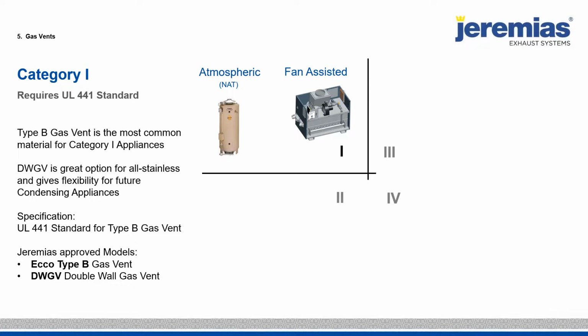So really what these categories tell us is what type of material to use on the venting side. So category 1 requires UL 441 standard. So that's type B gas vent. So UL 441 is a type B gas vent that can only be used on category 1 appliances. So we have a type B gas vent, and also our standard double wall gas vent has that listing as an option also. It's actually standard that the double wall gas vent includes that listing on it.